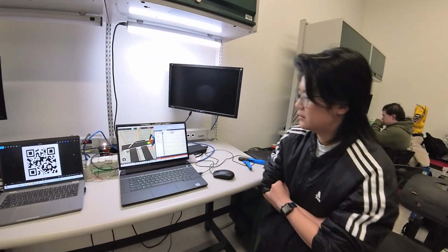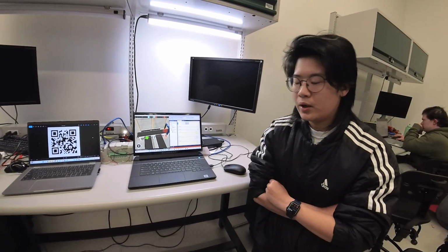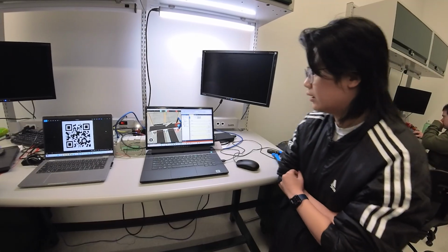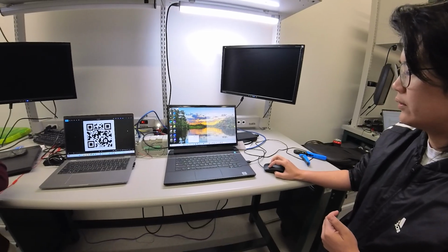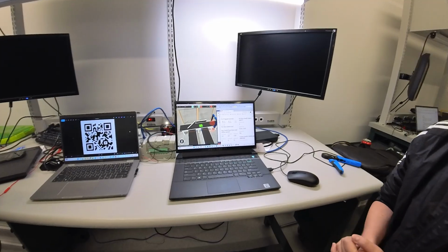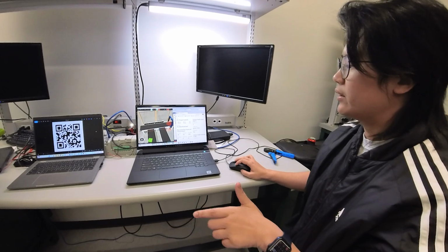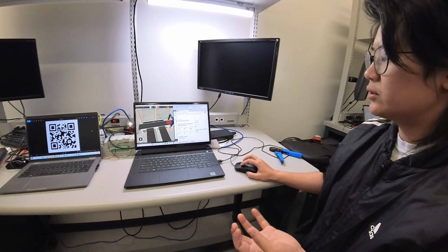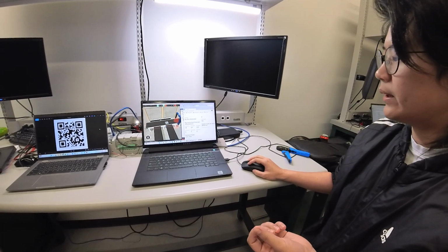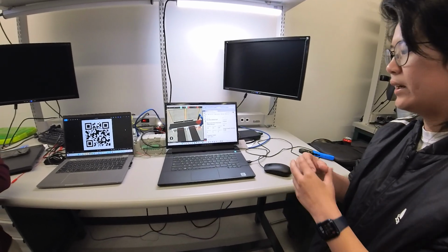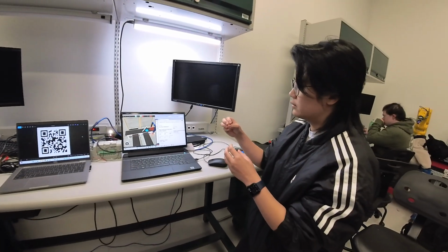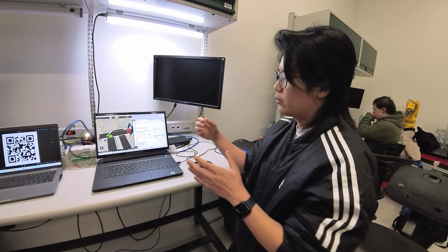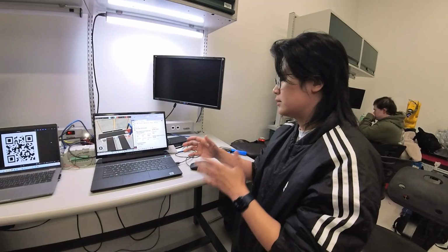Yeah, so once we have the PLC program, we configure the Modbus for each input and output. We send those data through MQTT to the database for future counting and control, like the start and stop. So we could see from the Streamlit over here, as my teammate will introduce the start and stop functions, it can also detect through the vision sensor how many blue, green, and metal boxes are being detected. I am also trying to collect information from the diffuse sensor, because I want to match up the amounts between the diffuse sensor and the vision sensor, since the vision sensor may make a mistake: it detected one, but it was sorted to a different channel, which makes the numbers different.